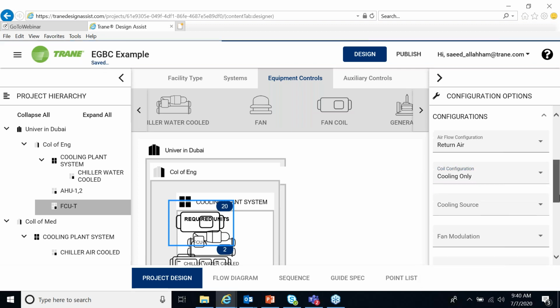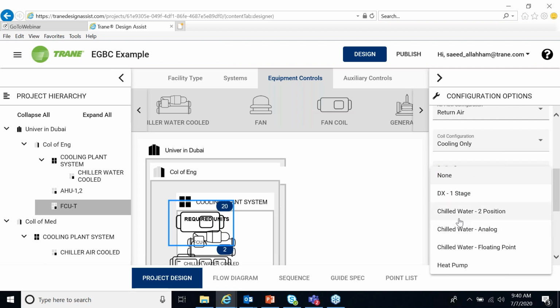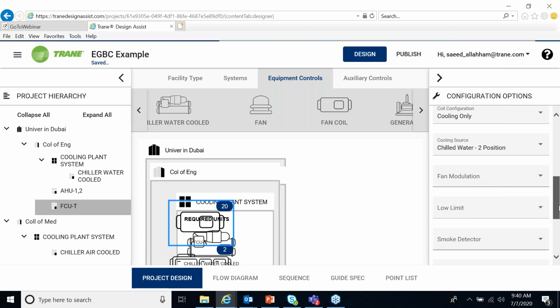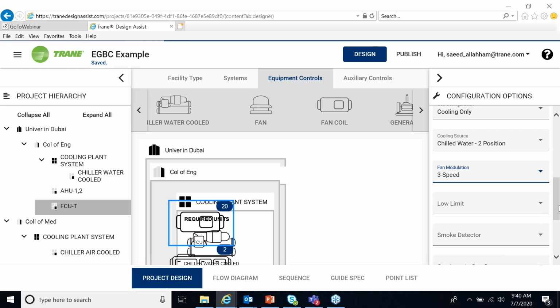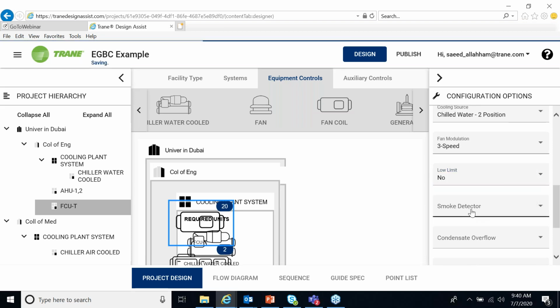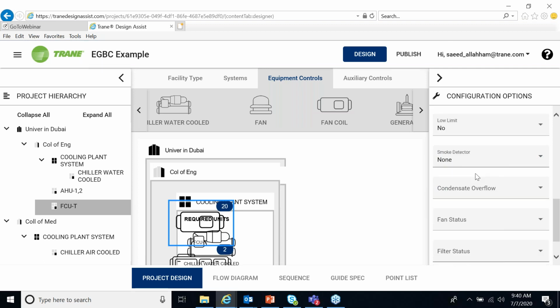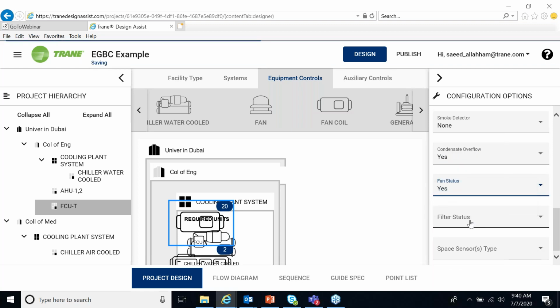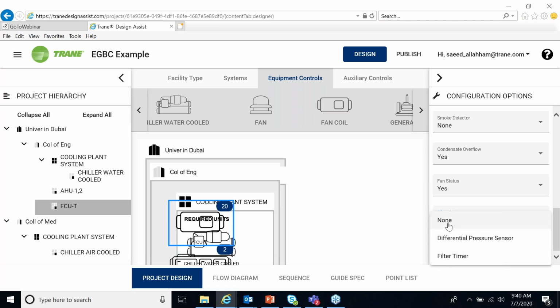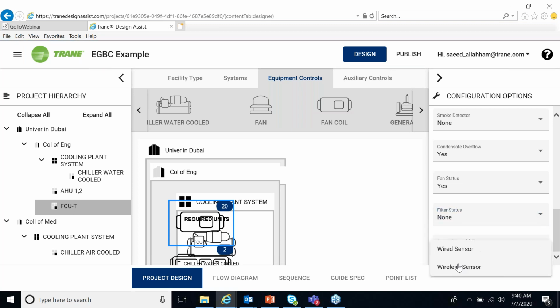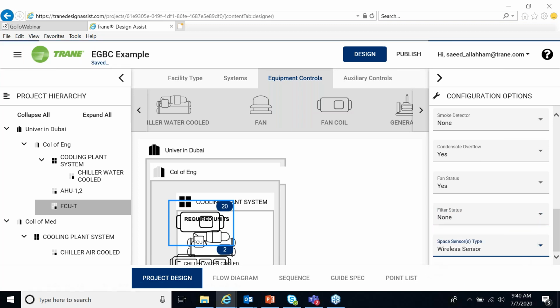Make it simple now. Cooling source, for the valve, we have chilled water. Analog is normally for the big coils, AHUs, two position for the FCUs. Fan modulation, let's say we have 3-speed. Low limit, let's say no. Smoke detector, let's say none. And then later you can change it. Okay. Condensate overflow, let's say yes. The fan status, we want to know the fan status. Filter status, we have differential pressure sensor or none, or timer, for example, none. Space sensor, it can be a wired or wireless sensor. And now we finish the configuration of the control for the 20 FCUs.